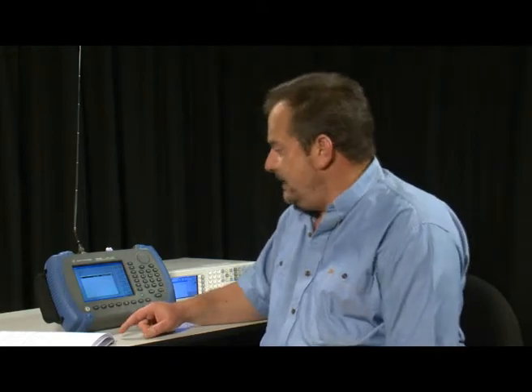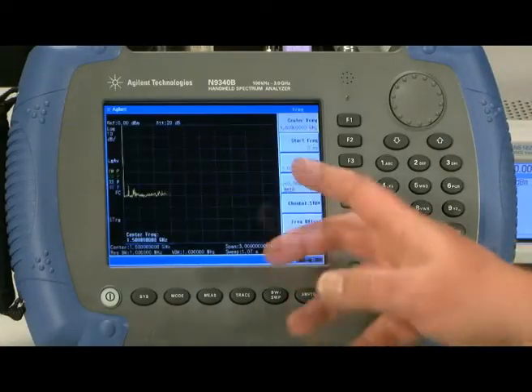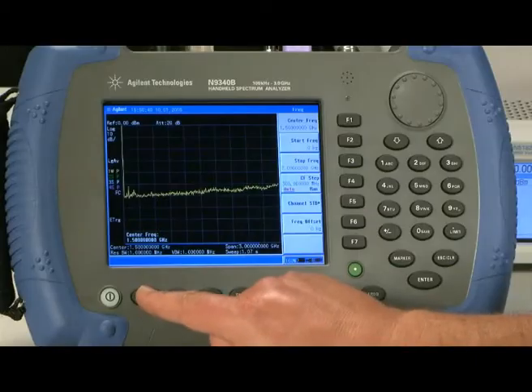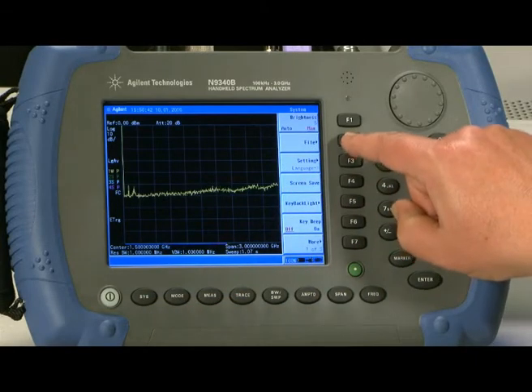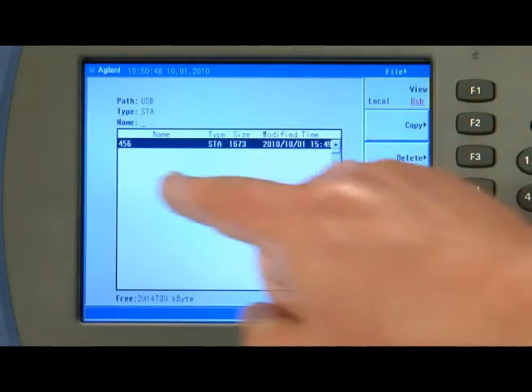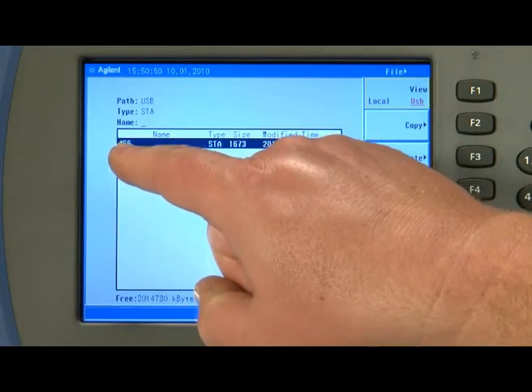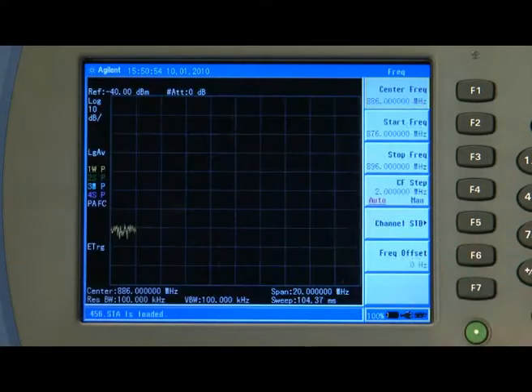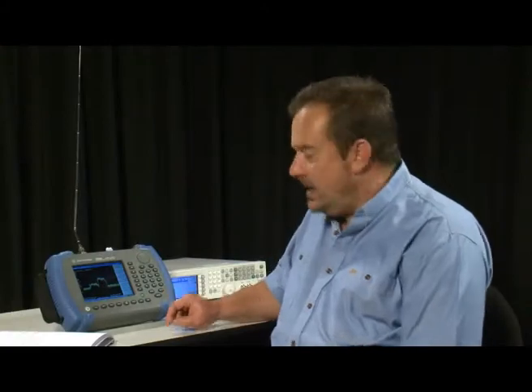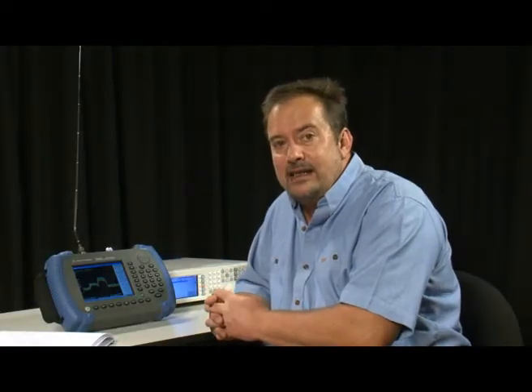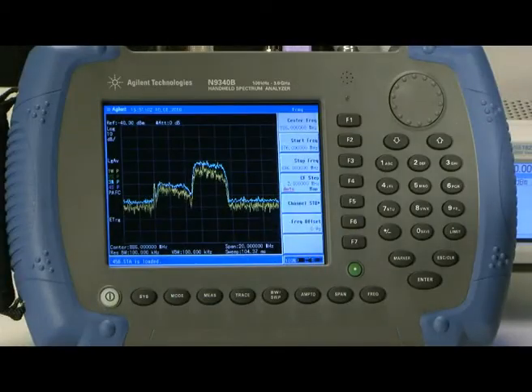Now let's say we have gone out on site and we want to recall that setup. Let me first of all preset the instrument to put it back to its factory default state. Then what I will do is I will press the system button and then file and if I change the view to the USB memory stick you can see here our file, our setup saved as 456. If I now press load now you can see immediately the whole instrument has been reconfigured to exactly the same setup that I had for the previous measurement of this base station.